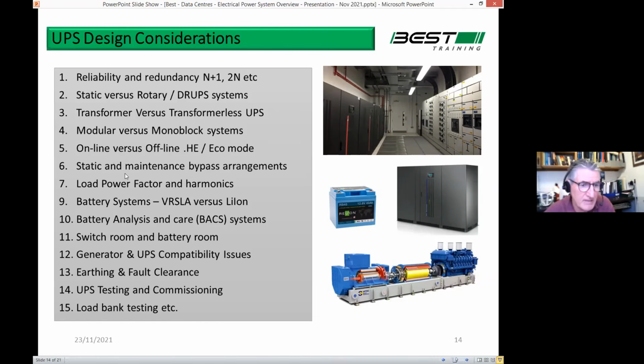Next thing is static and maintenance bypass, how you bypass the UPS, etc. Load power factor and harmonics, etc. Battery systems: the traditional battery is sealed lead acid. Lithium ion is now an option, and it's really gaining popularity. Then the battery analysis and care system, switch room, generator compatibility, and so on. There's a lot to take in, and I'm just looking at the clock as well. I have a few slides to go, and we're approaching question time, so I'll just move on anyway with that.